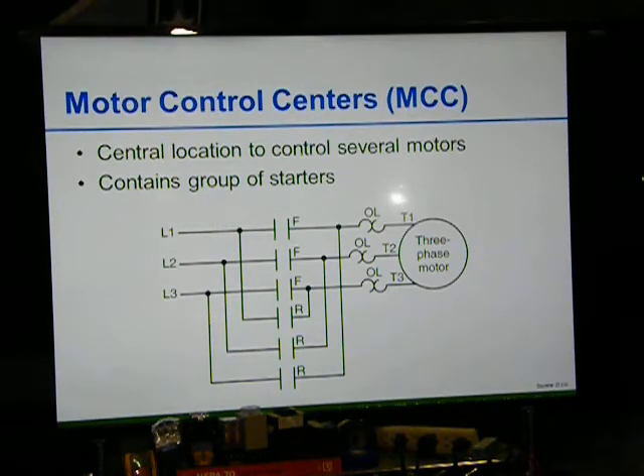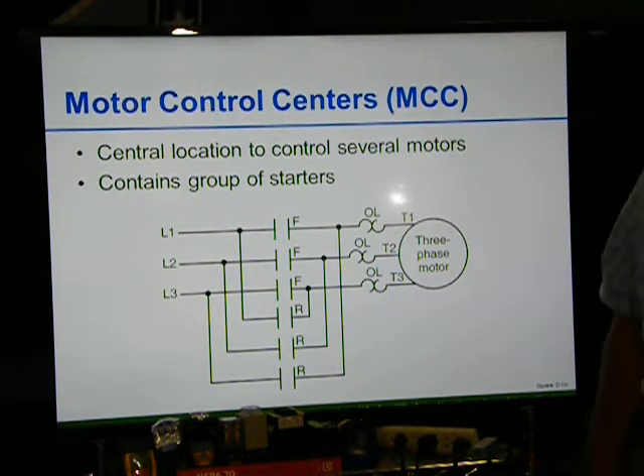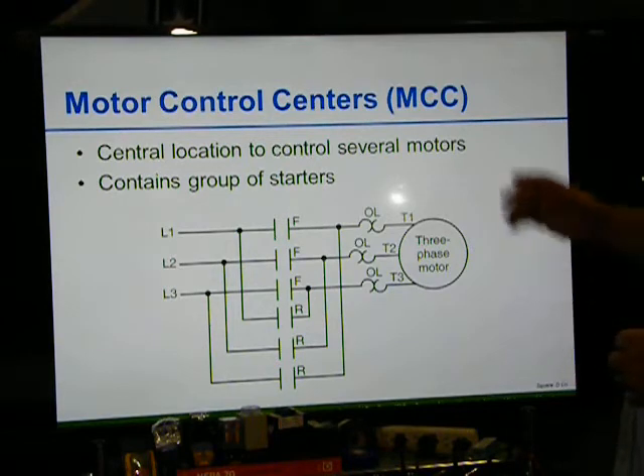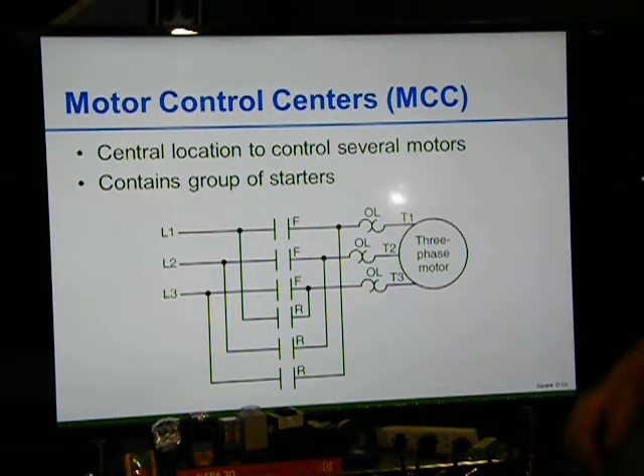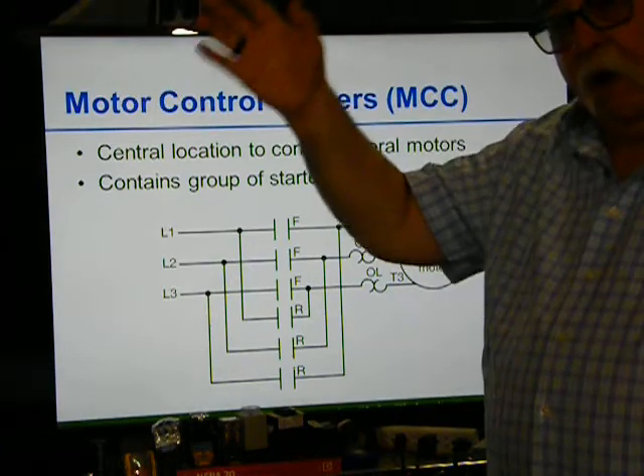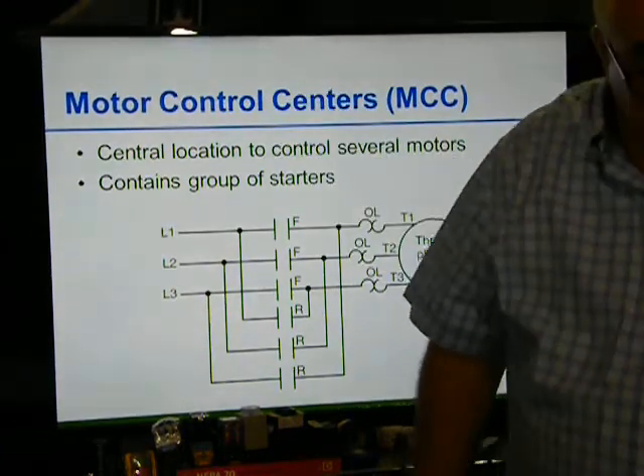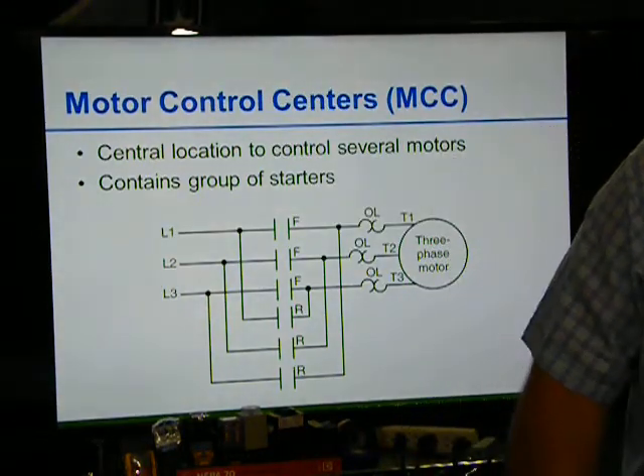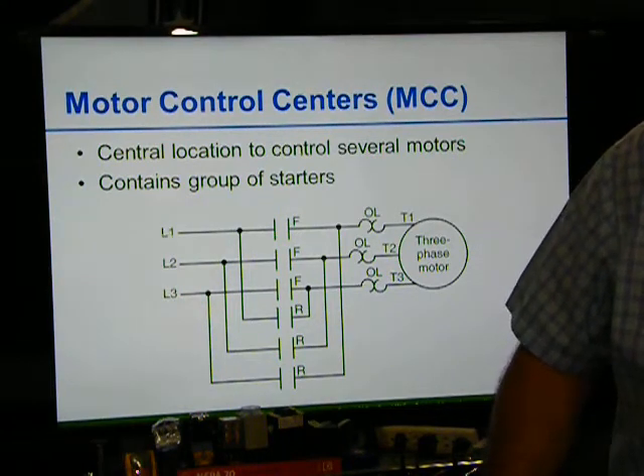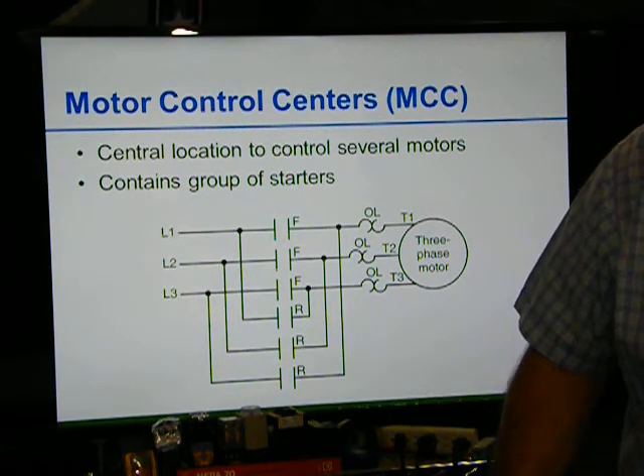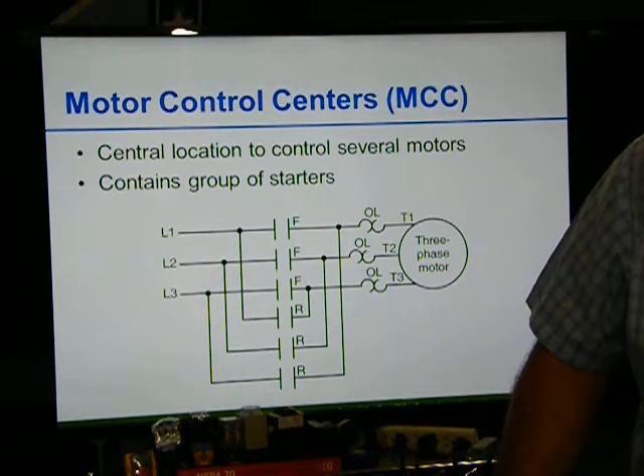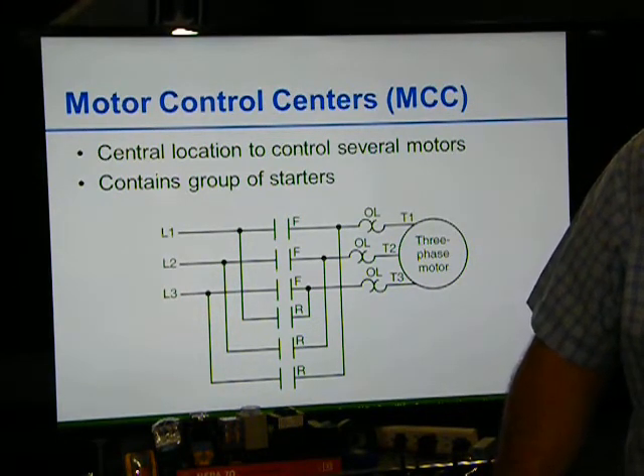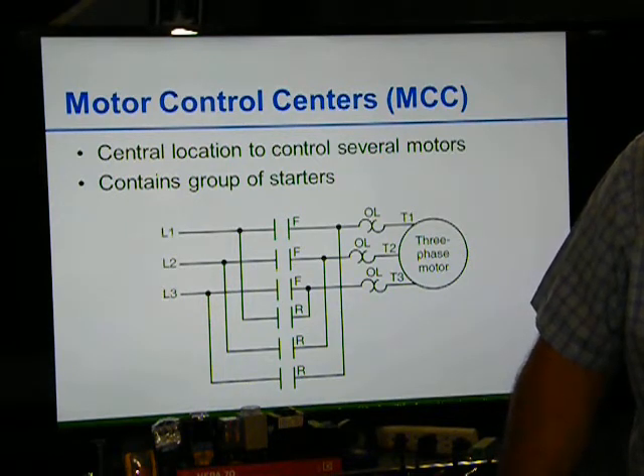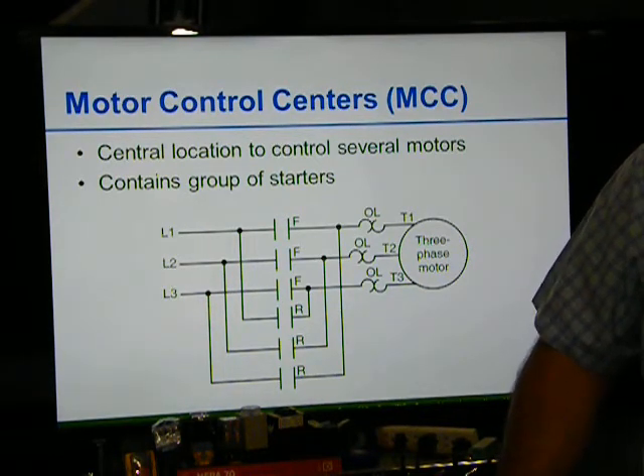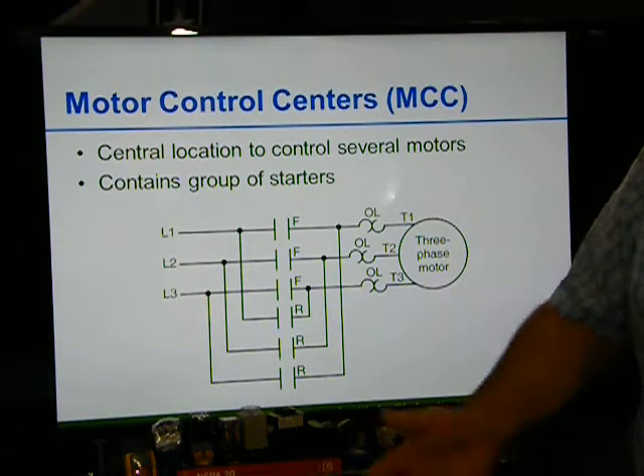Motor control circuits, MCC. An MCC is a motor control circuit. These motor control circuits, the MCCs, we use them to power up a lot of motors. Often several motors are controlled from a central location called the MCC. An MCC contains a group of starters. MCC structure is made of vertical sections and buckets.